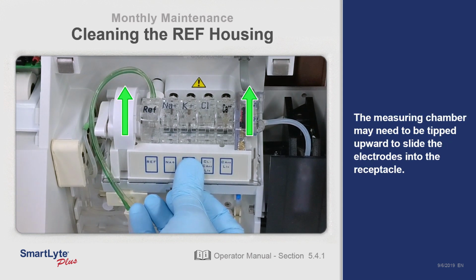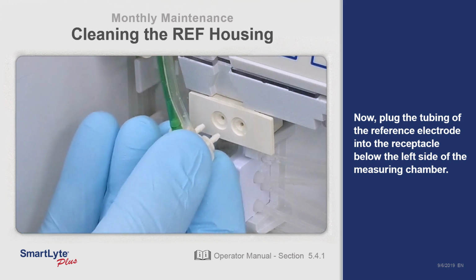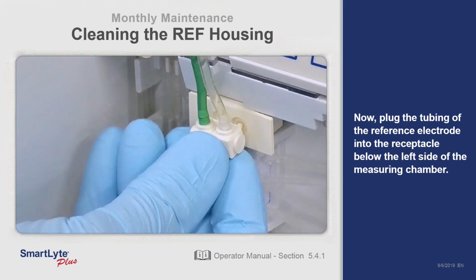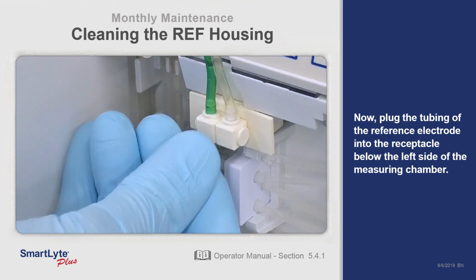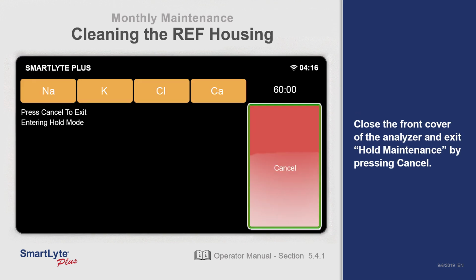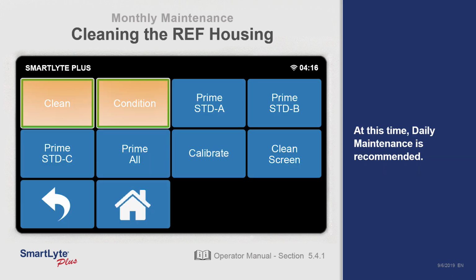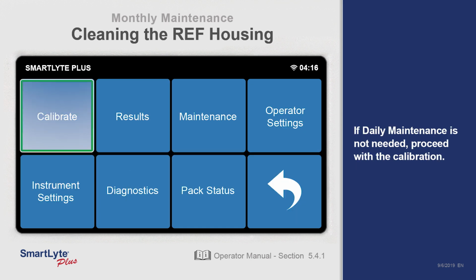The measuring chamber may need to be tipped upward to slide the electrodes into the receptacle. Plug the tubing of the reference electrode into the receptacle below the left side of the measuring chamber. Close the front cover of the analyzer and exit Hold Maintenance by pressing Cancel. At this time, daily maintenance is recommended. If daily maintenance is not needed, proceed with the calibration.